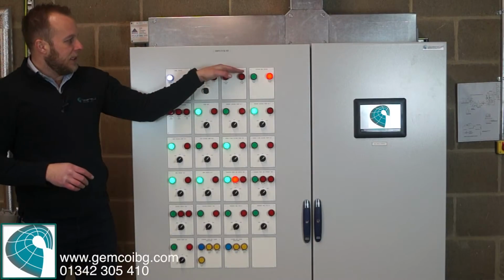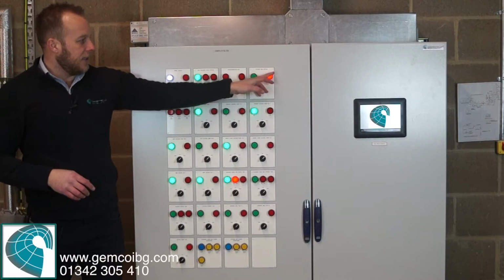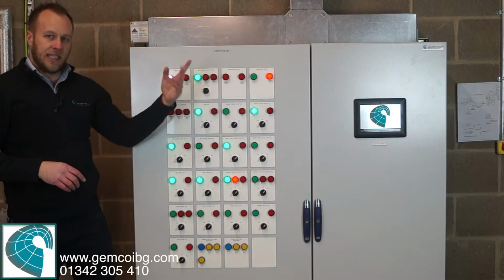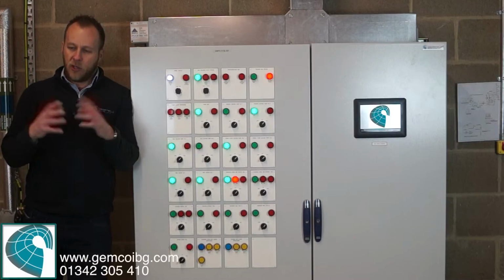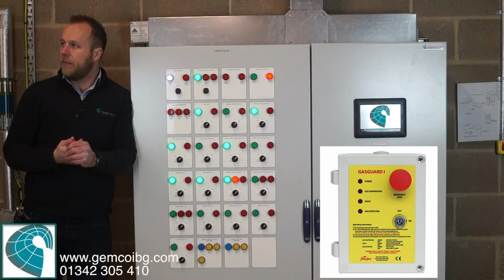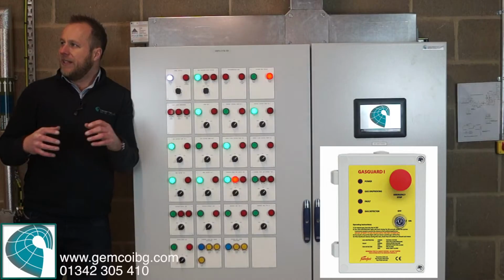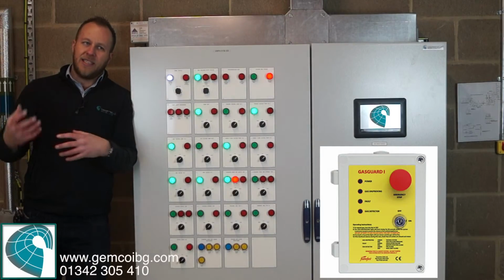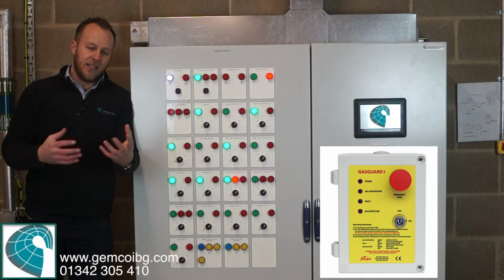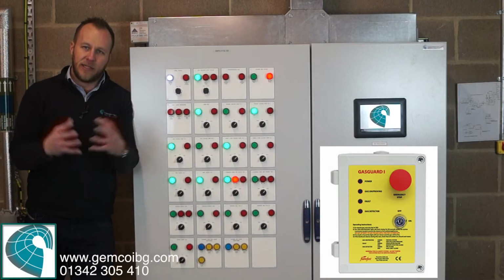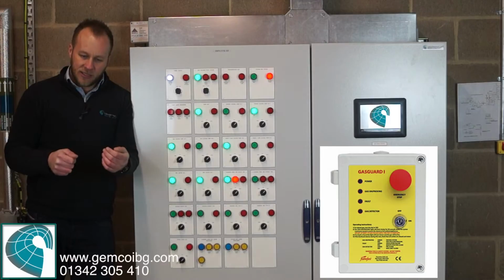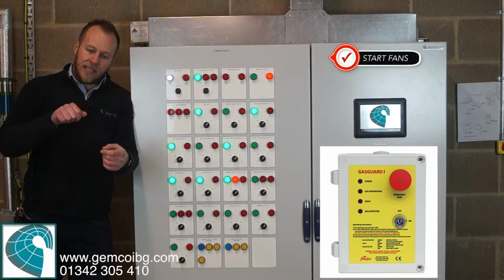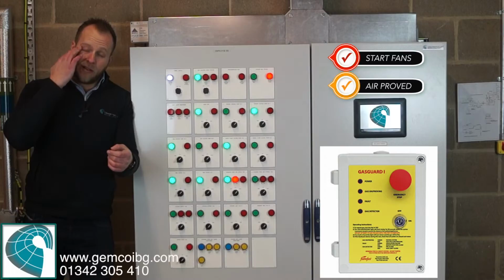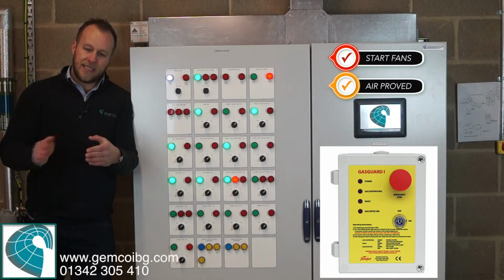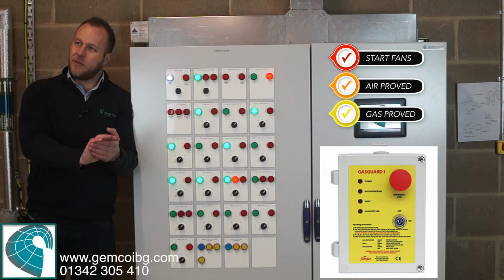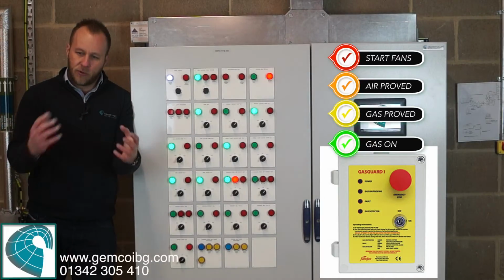Okay, so that is those two lamps there, and then this kitchen gas status. In the kitchen, I'll go up and show you that system independently, but you've got a gas proving system, which I'm sure someone may or may not have shown you how to use. When you've got forced ventilation into a kitchen, which you have, with two fans and gas appliances, you have to have a gas proving system to meet regulations. That means the staff have to be aware that they need to start the fans. There's a key switch up there to start the fans, and then when they want to use the gas, they have to start the fans, then start the gas sequence, and the gas panel will go through a sequence of proving the gas.